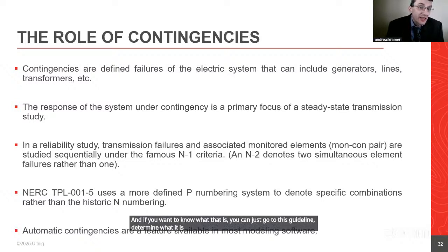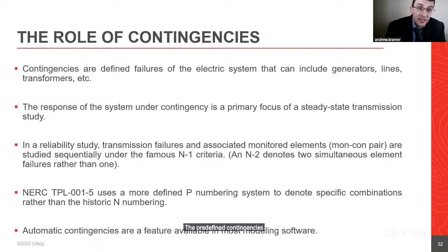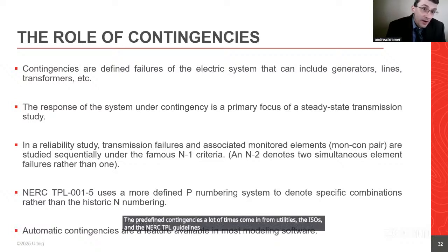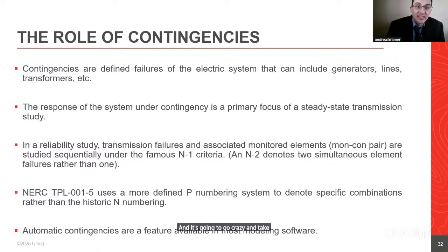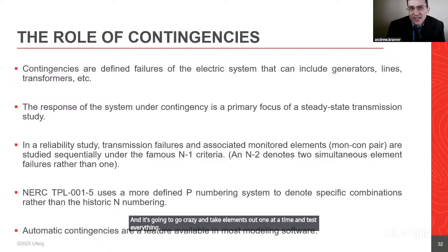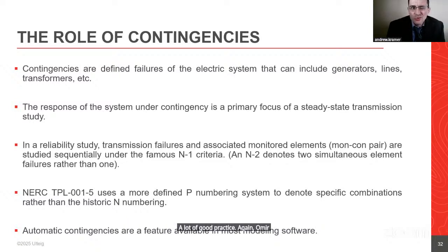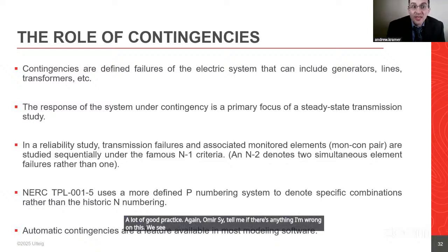Now, the other thing that I saw come in is automatic versus predefined. The predefined contingencies a lot of times come in from utilities, the ISOs, and the NERC TPL guidelines. You can allow these other models to put in automatic contingencies, and it's going to go crazy and take elements out one at a time and test everything. A lot of good practice. Again, Omir Sai, tell me if you think I'm wrong on this. We see in the utility that we allow the predefined, and then we'll also enable automatic as a sanity check at the end of the day.